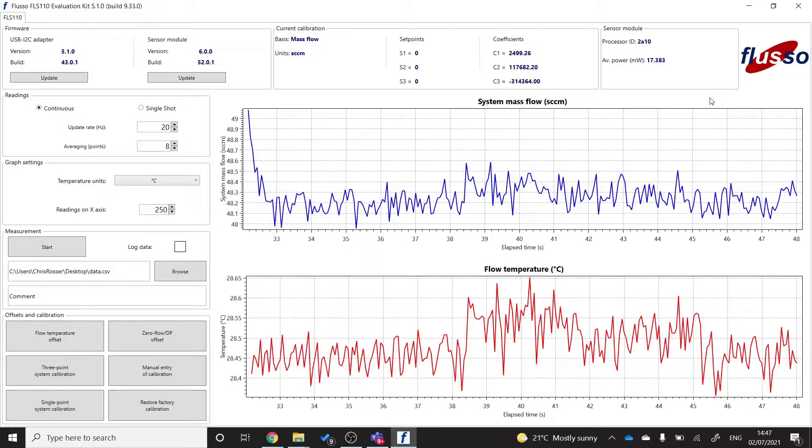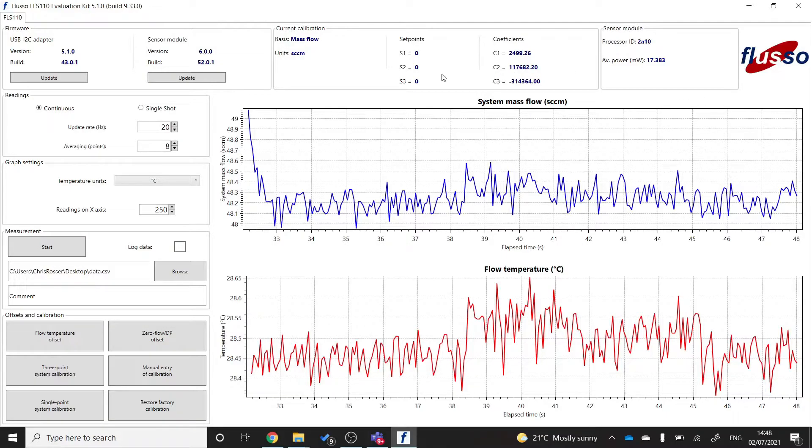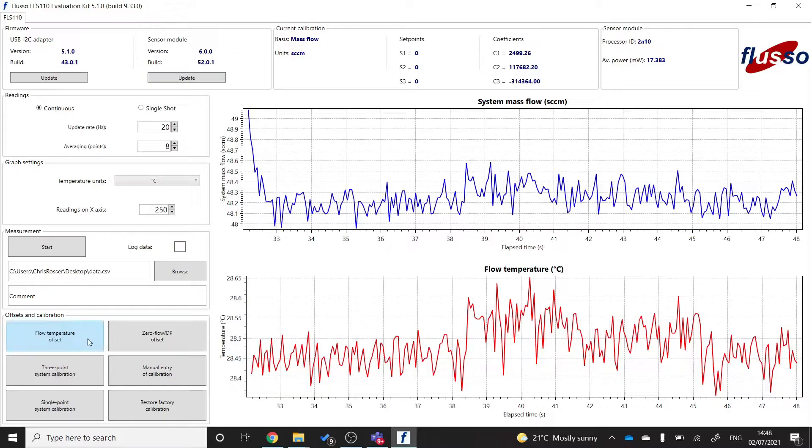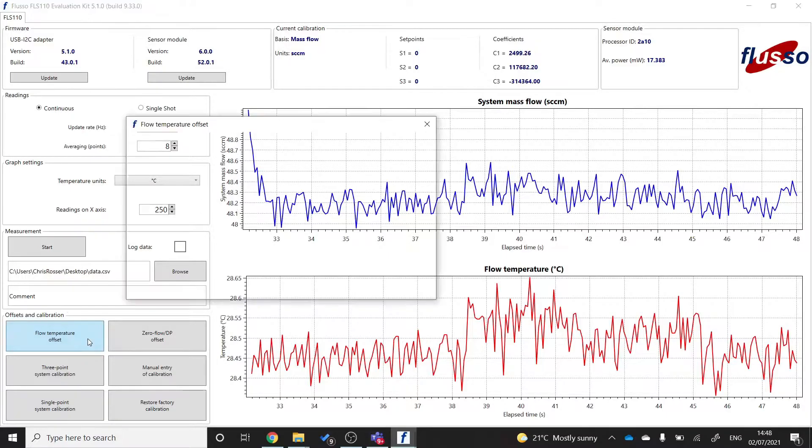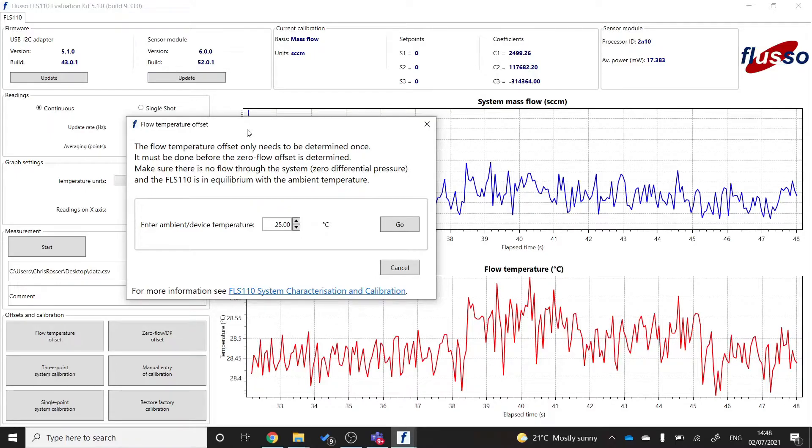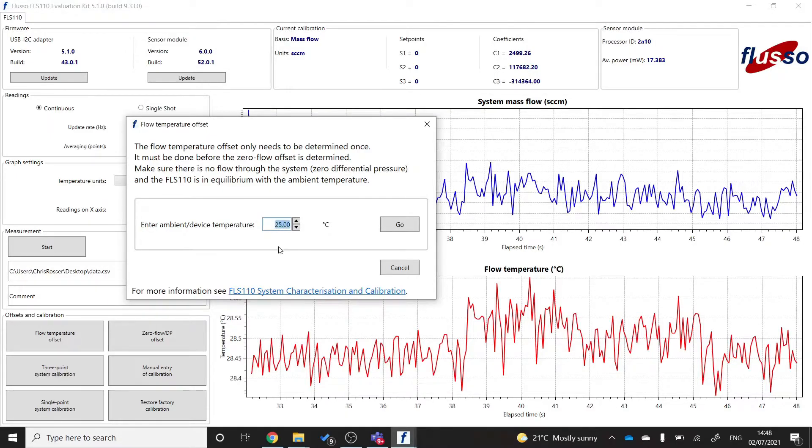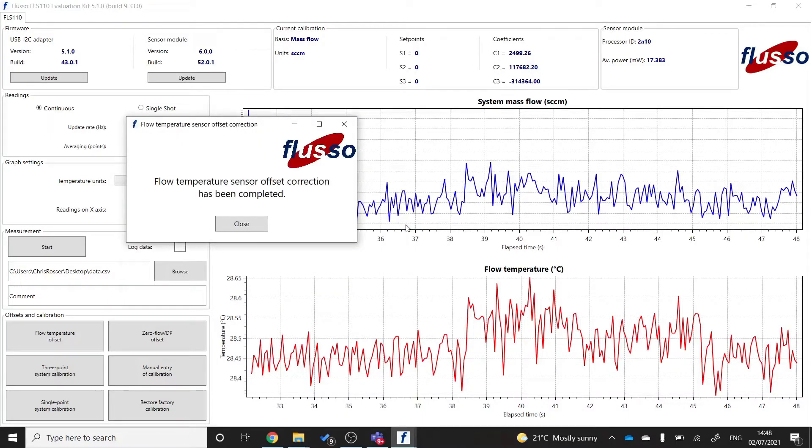Once you're happy that you've got the sensor measuring flow, the next step is to calibrate the sensor for your particular system. And to do that, we're going to use this offsets and calibration menu down there. We're going to start with flow temperature offset correction. If you click that button, you'll see this dialog box pop up and you'll want to enter the ambient temperature that the sensor is currently at, which I know in this room to be 27 degrees. And that will complete the temperature offset correction.